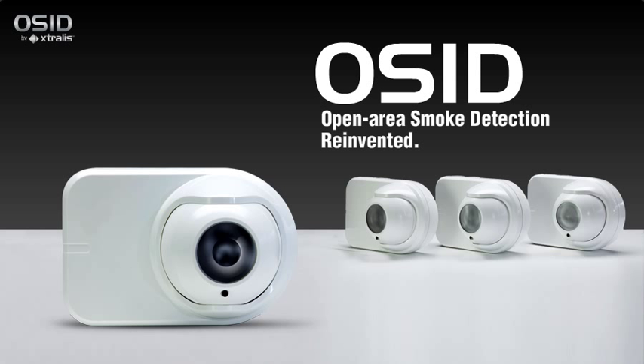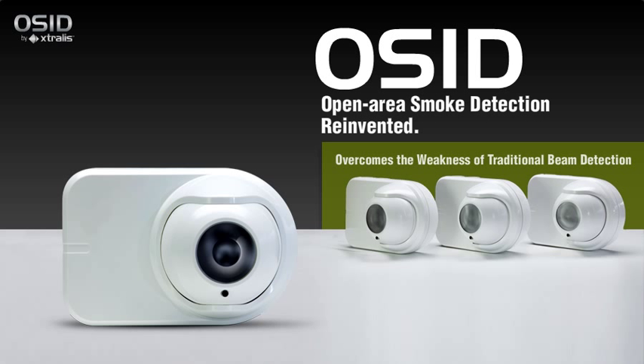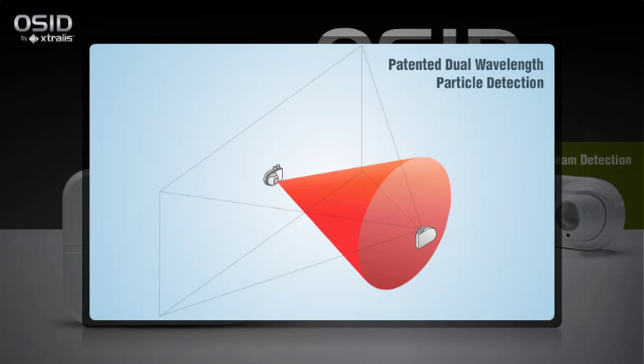Xtralis has reinvented open area smoke detection with its latest patented innovation, Open Area Smoke Imaging Detection or OSID, which overcomes the weaknesses of traditional beam detection to provide reliable, cost-effective protection for open spaces requiring only standard sensitivity detection. In its simplest configuration, OSID uses one imager, a camera-like device with a wide field of view, and a wired or battery-powered emitter roughly aligned on the opposite wall within the protected area.